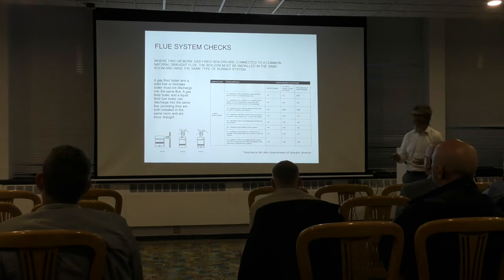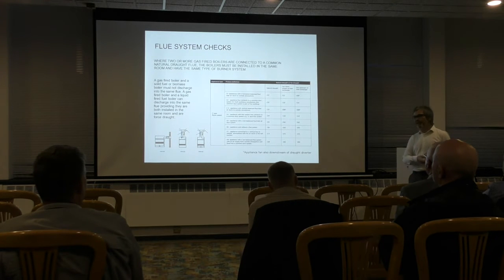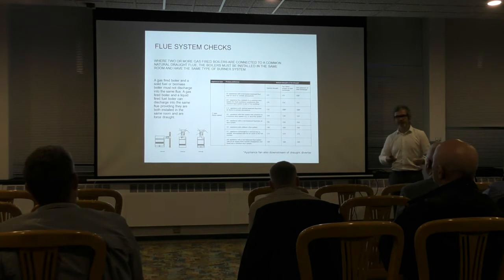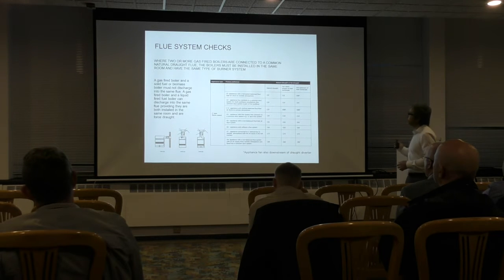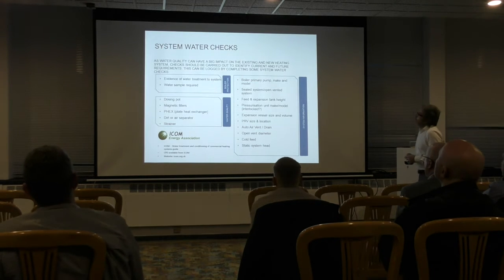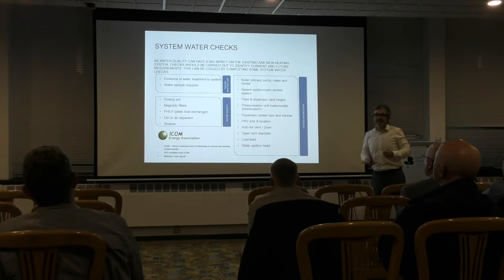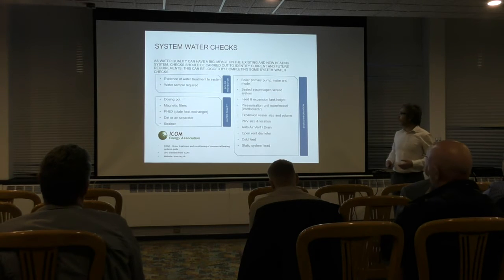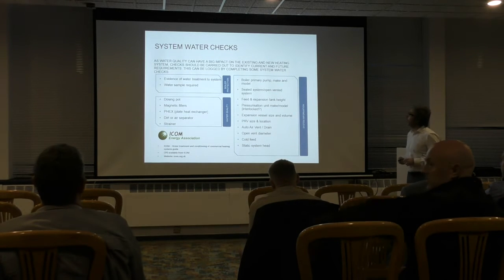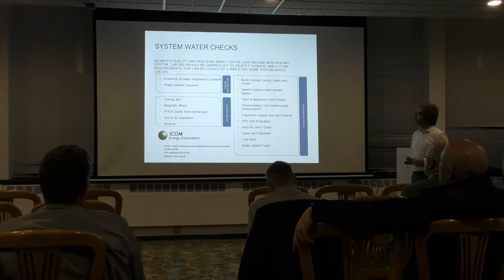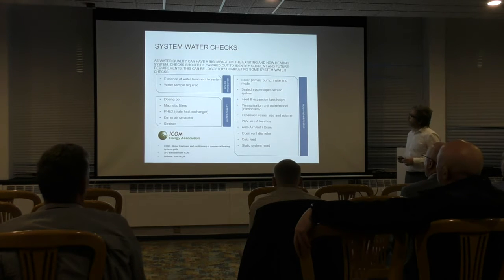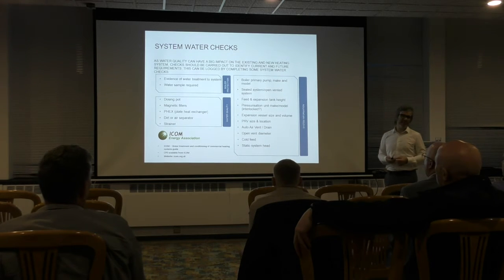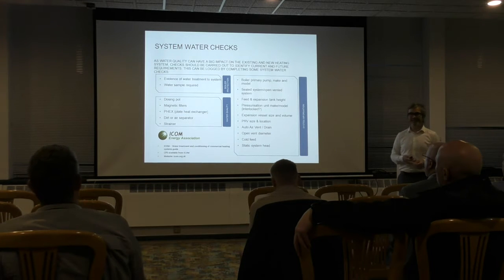And other things like you wouldn't put a CHP or a biomass boiler or whatever on the same flue system as a premix condenser boiler. Moving on from that, so we've looked at all of our ventilation, our flue, etc., and our legislation, and we're now looking at the system water, and really, I suppose the first thing really is water treatment, and I'd probably say water treatment is probably one of the first things that gets neglected on a heating system.